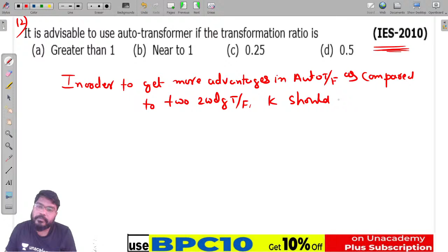K should be nearer to 1. But here the range of K in an auto transformer is greater than 0.33 (33%) and less than 1. The desirable value of K is nearer to 1, that is, K is less than 1 but nearer to 1.